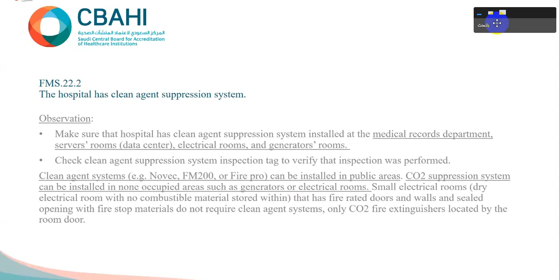And in this case, FM200 is preferable. The clean agent does not mean any brand name. FM200, Fire Pro, Novec, it doesn't matter. But usually it seems to me that FM200 is the most popular system, not only in Saudi Arabia, even in the States. Usually we install this kind of clean agent in public areas. CO2, carbon dioxide, is a clean agent, but could be used as a total flooding system and installed in non-occupied areas like generators and electrical rooms. FM200, Novec, Fire Pro, all are accepted.